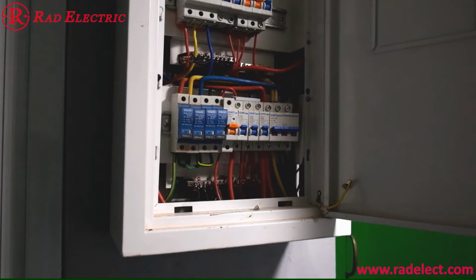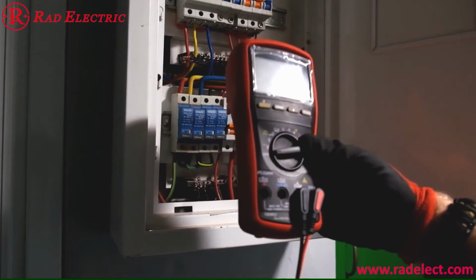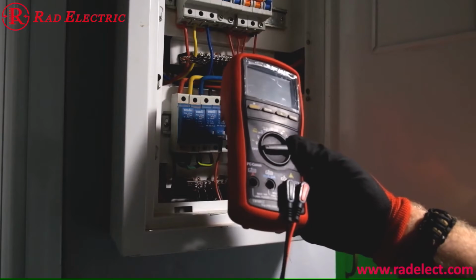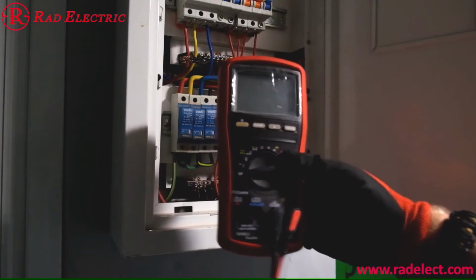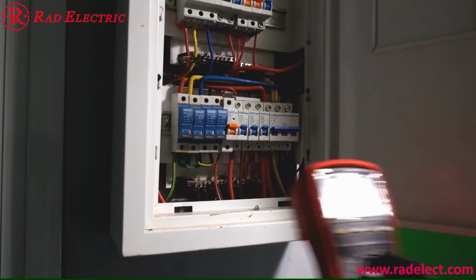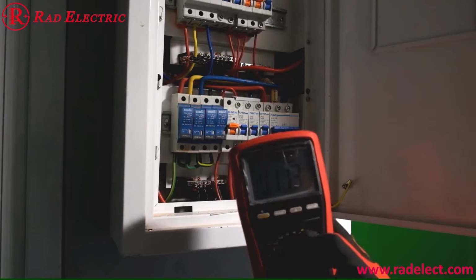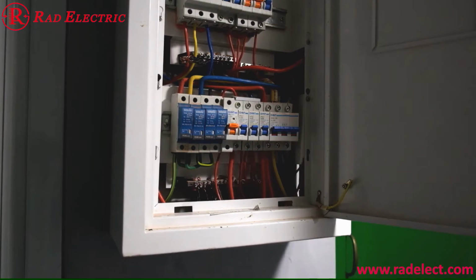Now, if you're not using one of these test probes and you're using a multimeter, there's a few things you need to know. One of them is make sure that your meter is safe and has a fairly decent cat rating, such as this Brymen BM812 or the 829s, which are cat 4 1000 volts. You can switch it onto AC volts like so, and then take your probes pretty much phase to phase, same as we did before.